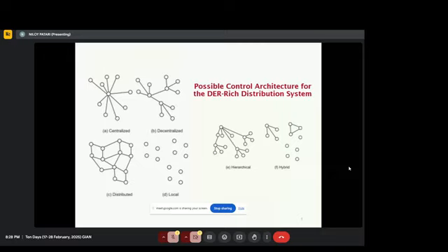Obviously, I'm giving an example, but they can still operate. In certain situations, they can take an estimate or whatever. But what I'm saying is, there is a possibility that there is important information they need to gather, they are not able to do that at the ADMS level, and they could not come up with any solution. So this is termed a single point communication failure. The communication infrastructure has to be extensive, dedicated, and available all the time. So this is one disadvantage of centralized.